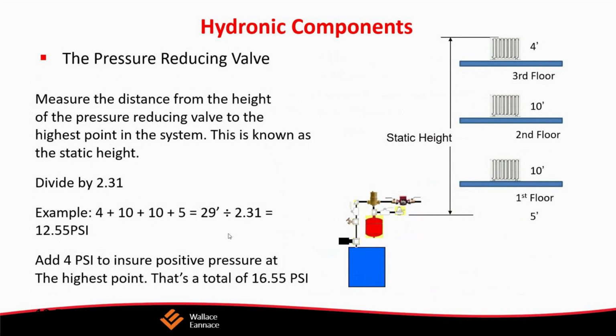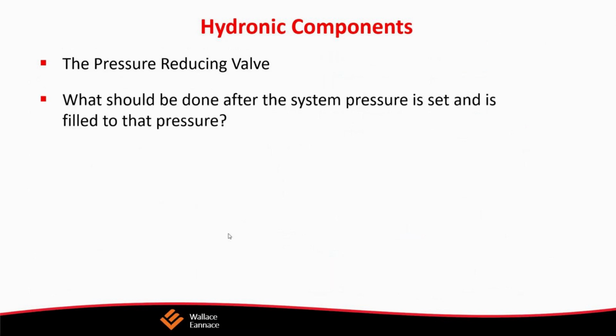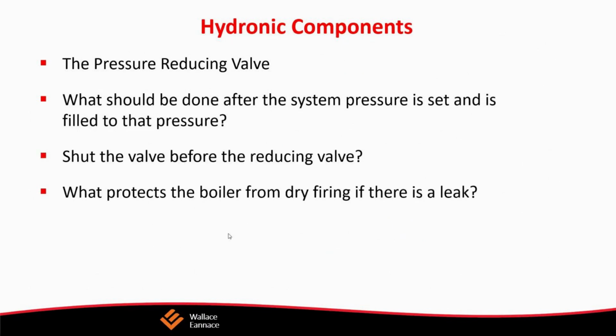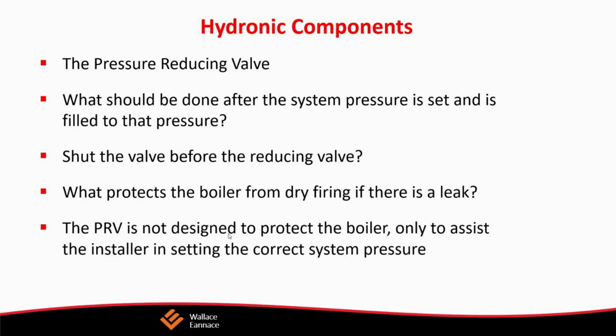Let's talk a little bit about the pressure reducing valve. It's also known as the fill valve. And when it's supplied with a relief valve, it's also known as a dual unit. It allows the system to install the fill pressure at the required pressure. It usually comes preset to 12 psi. It's adjustable. 2.31 feet per pound times 12 psi means that it'll raise the water 27.71 feet.